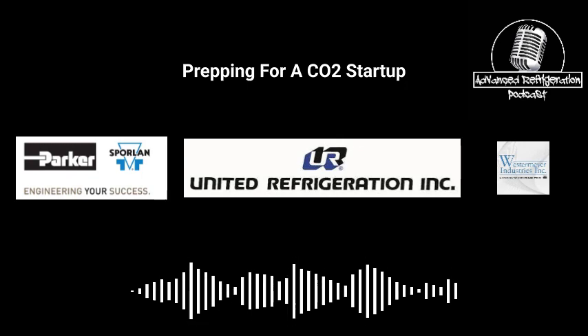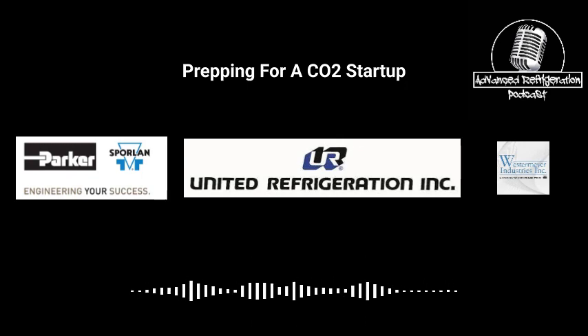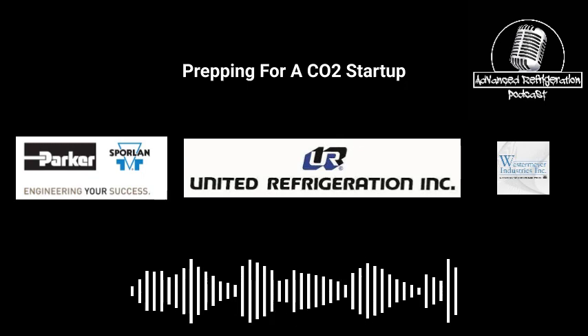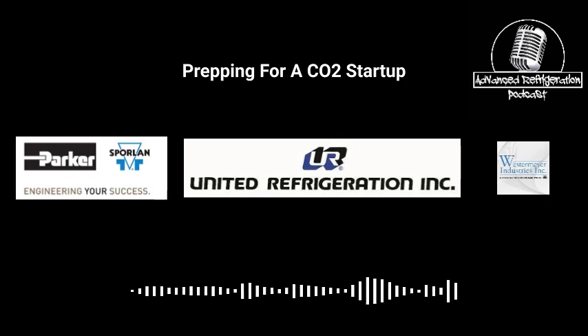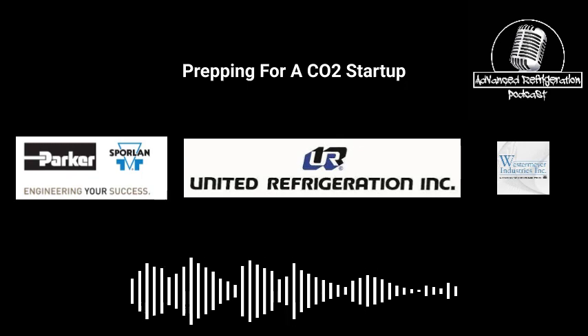I really wish all these manufacturers would put in circuit switches and just do inputs to shut down each individual circuit, because it'd make startup a lot easier, but they don't. They usually do it one of two ways as far as the restart function. They either do it off of time delay, right? So the first case is let off after 10 seconds, and then 120 seconds after, and 120 seconds after, and usually that's how they cycle.